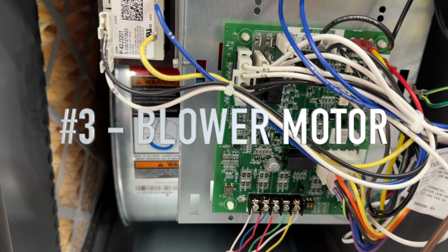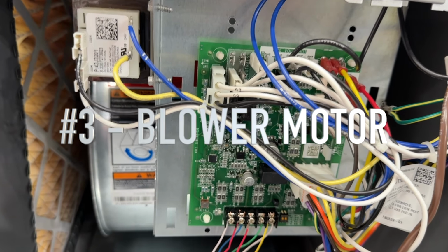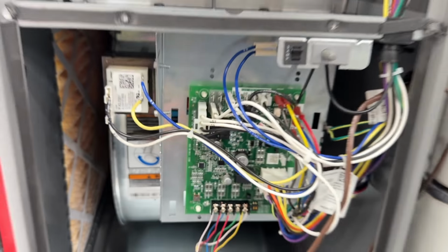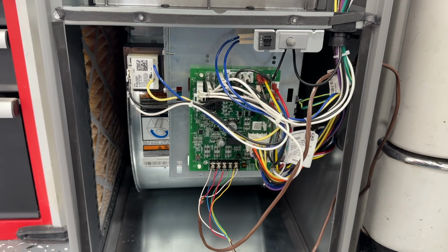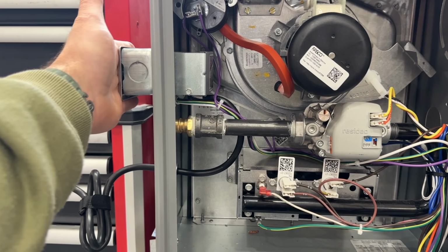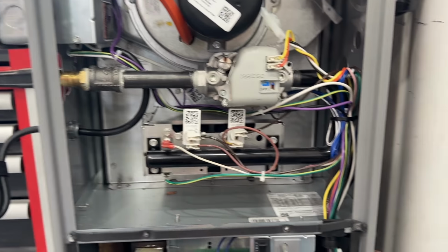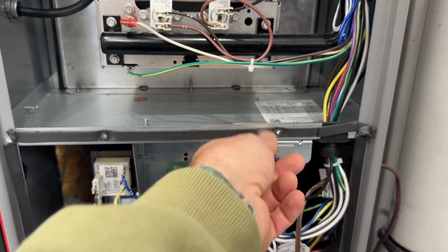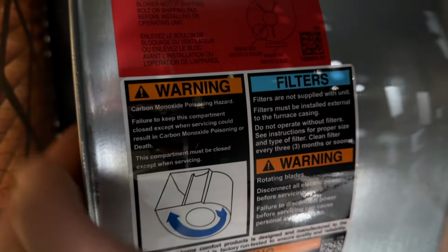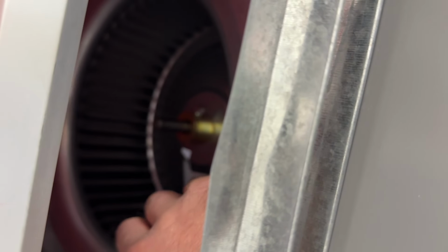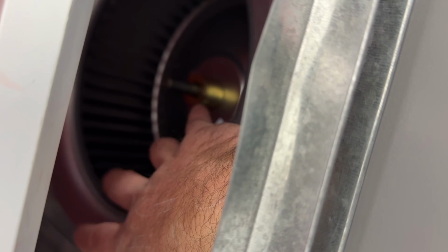Number 3 is going to be your blower motor. This is actually a pretty common thing. So the first thing that I like to do when I'm diagnosing a blower motor, make sure the switch is turned off or it's unplugged, make sure that your door switch is disengaged, and all we're going to do is reach in back here and spin this blower motor. I'm going to pull this filter out just to show you what we're doing here. So basically we're just going to reach in and we're going to spin that blower wheel.